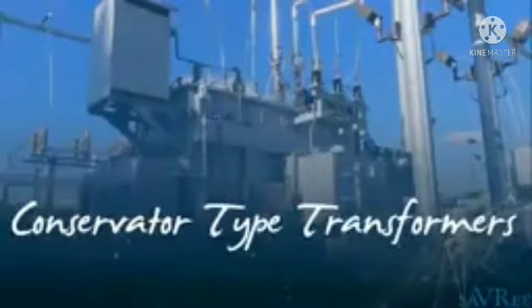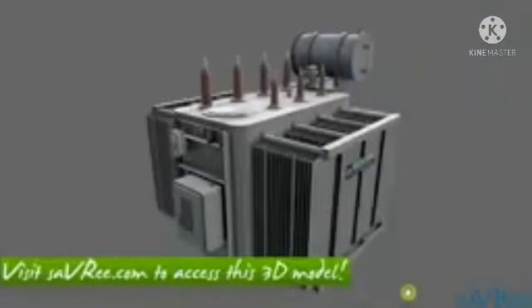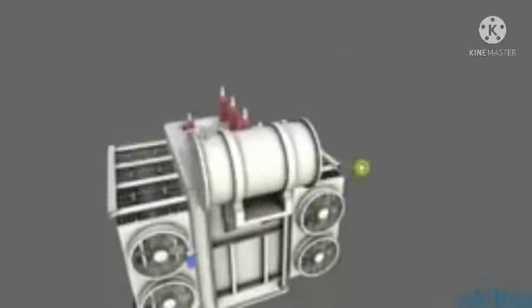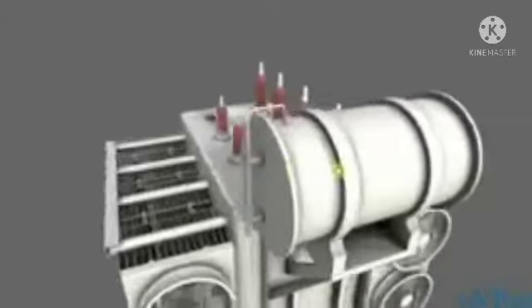Let's now have a look at the conservator type transformer, which I think is the most interesting and has a lot more components compared to the dry and hermetic type transformers. So here we are, we're now looking at a conservator liquid immersed transformer. The reason it's called a conservator type transformer is because of the tank on the back, which is known as the conservator tank. That is this item here.